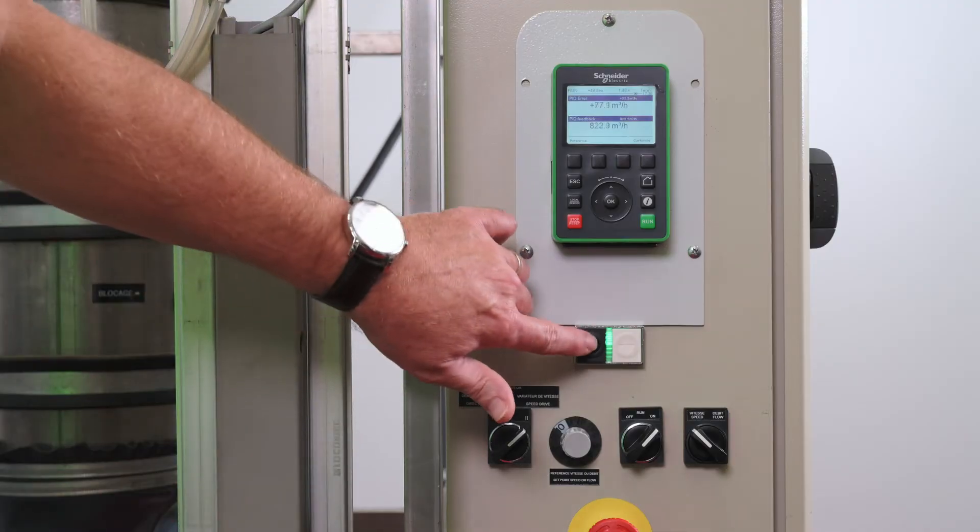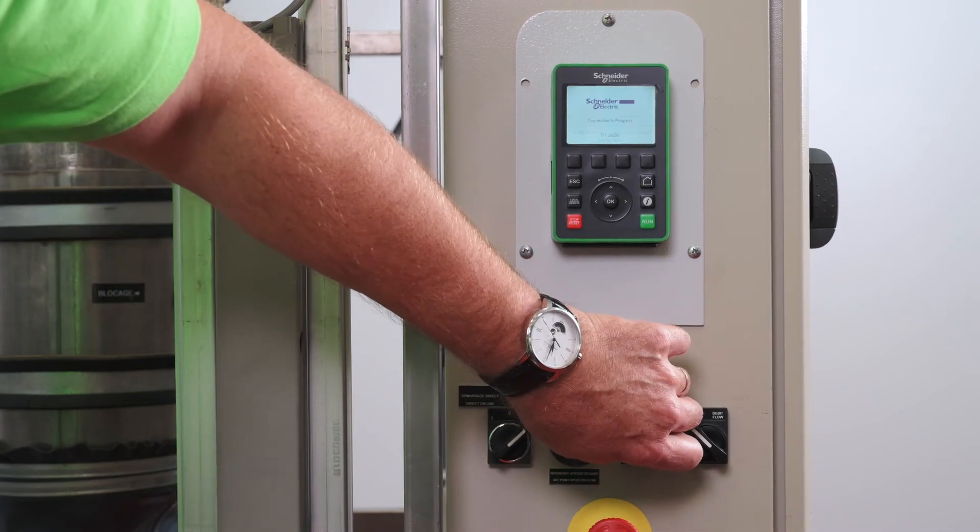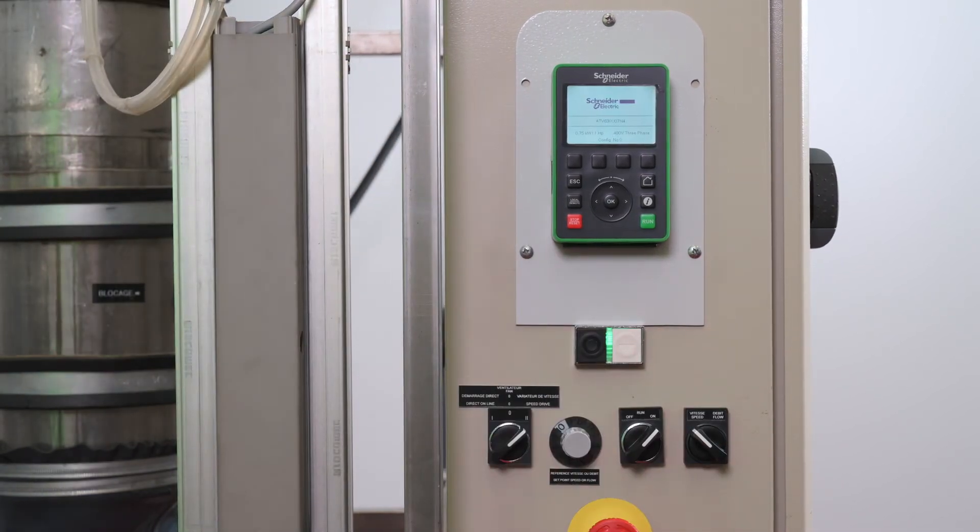The Catch on the Fly function allows you to avoid unwanted deceleration down to zero when the fan rotates on freewheel, and also to avoid any overcurrent inside the motor because of slowdown.